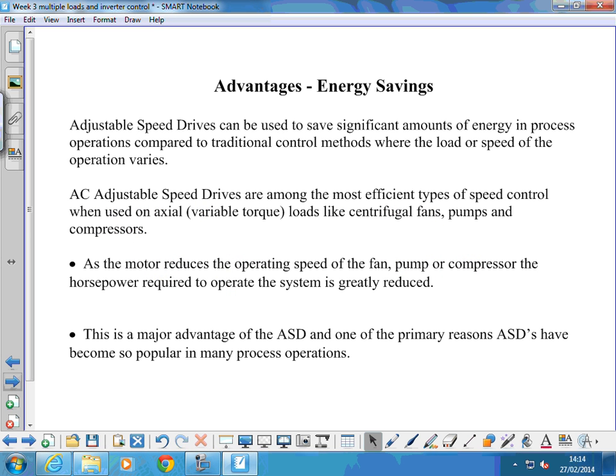So, energy savings. They can be used to save a significant amount of energy in process operations compared to traditional control methods, where the load or the speed of the operation varies. Adjustable speed drives are one of the most efficient ways to do speed control when used on variable torque loads like centrifugal fans, pumps and compressors. As the motor reduces the operating speed of the fan, pump or compressor, the horsepower required to turn it is reduced. It's a major advantage of the ASD, one of the primary reasons that they became very popular in process operations, because they reduce the energy required.